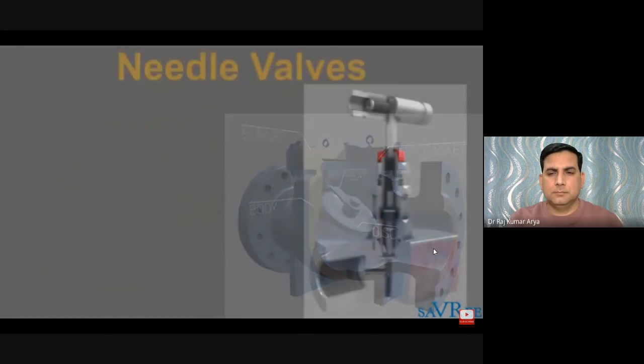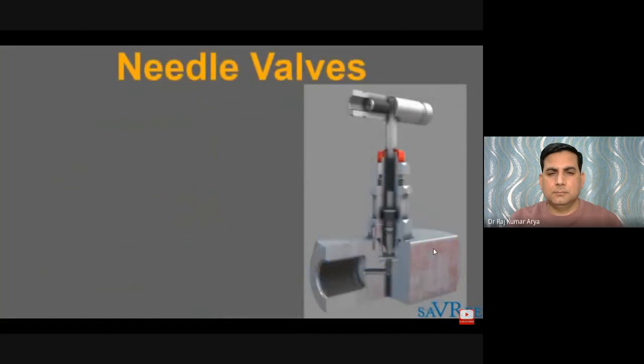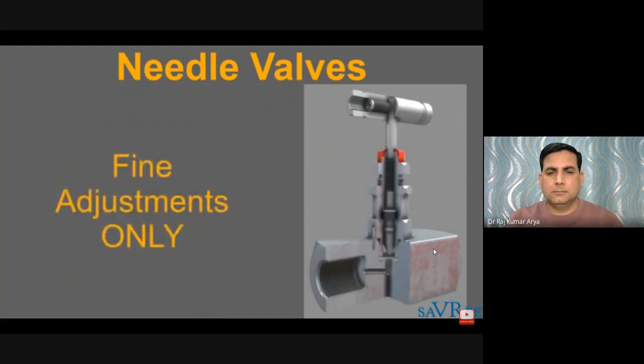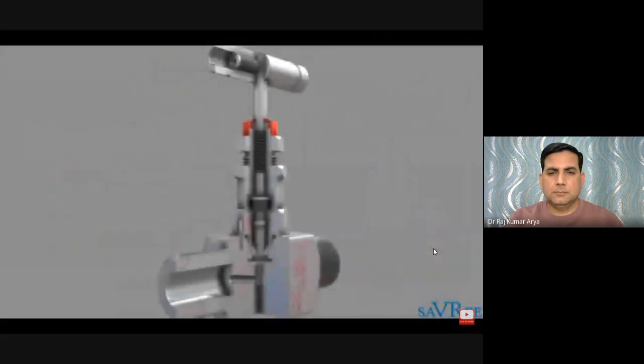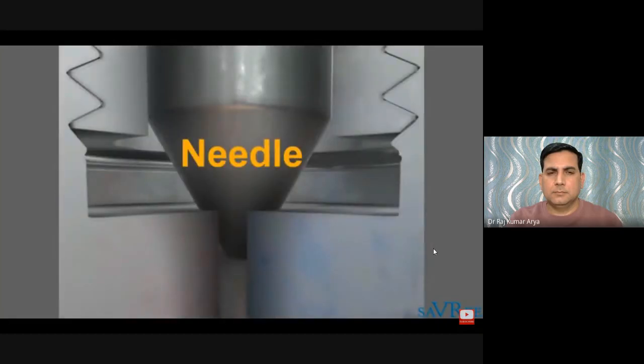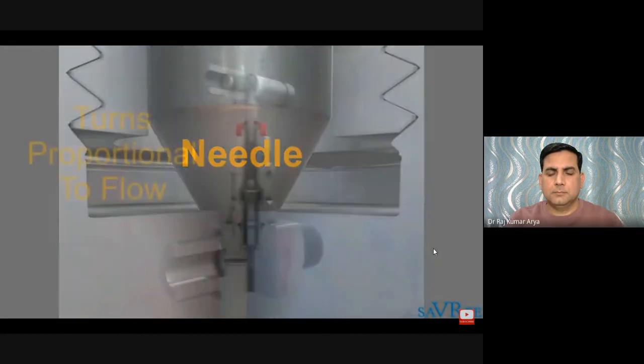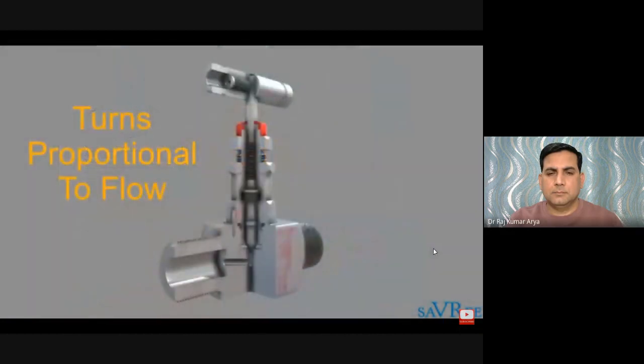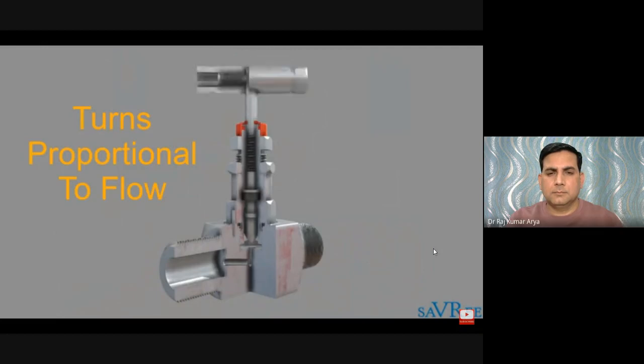A needle valve is used to make relatively fine adjustments in the amount of fluid flow. Its most distinguishing characteristic is the long tapered needle-like point on the end of the valve stem, which acts as a disc. The needle passes through the orifice before it seats, permitting a very gradual increase or decrease in the size of the opening. Needle valves are frequently used as metering valves, because the number of turns of the hand wheel can be directly correlated to the amount of flow.